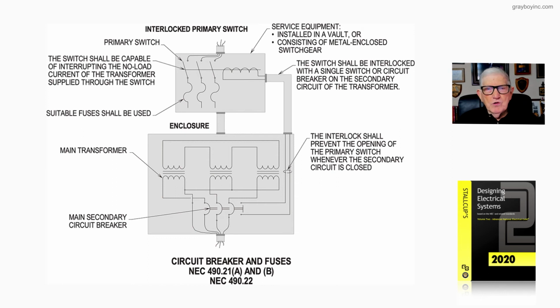Now, the enclosure at the bottom, the main transformer that you see there, the main secondary circuit breaker you see is outlined there, and the interlock, reading to the right of the illustration, the interlock shall prevent the opening of the primary switch whenever the secondary circuit is closed. Now, we read those two last sentences in the code just previously, and it's stating what you see here in this illustration. But I thought maybe you might enjoy more and get more benefit from me actually reading you the requirement instead of paraphrasing it as you see here in the illustration.